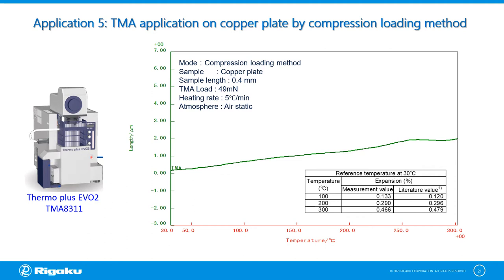This figure shows the TMA compression loading measurement result of copper plates on 400 micrometer thickness direction. In samples that have minute expansion, the differential type compression loading method is effective. Comparing the expansion results of this sample to the literature values at the base temperature of 30 degrees, the measurement expansion results are within 10 percent.